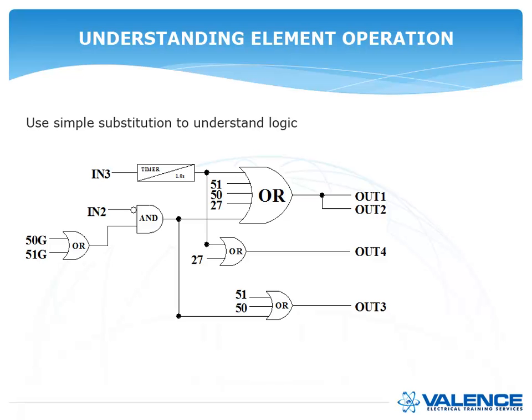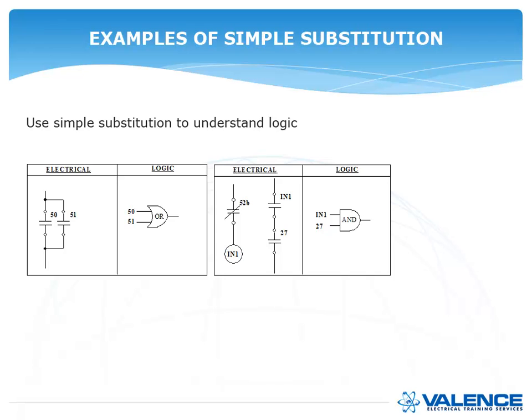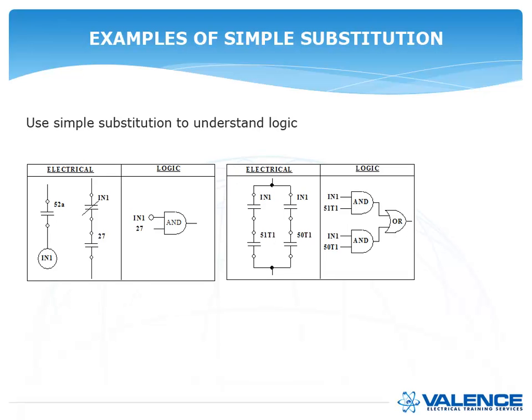So this particular logic scheme could be quite complicated, but you can break it down into its base components. You can use simple substitution to understand the logic. So if my logic says 50, 51 into an OR gate, like I said before, that's two contacts in parallel. Or if I have an IN1 and a 27 going into an AND gate, that would be two contacts in series. Now, if it's NOTed, if it's a 52A and then you NOT it, then that would be the same thing as having a normally closed version of that IN1, like it's shown on the left-hand side. And we already went in detail about two contacts in series and in parallel to create that kind of logic diagram.